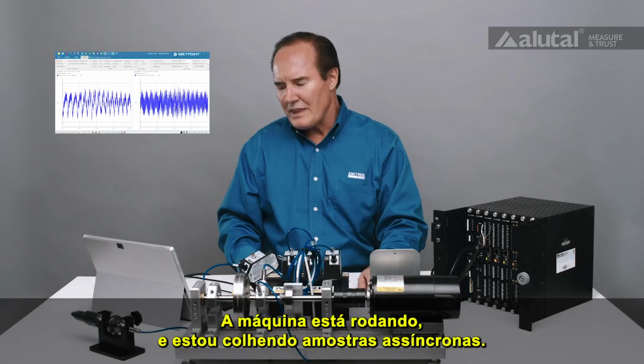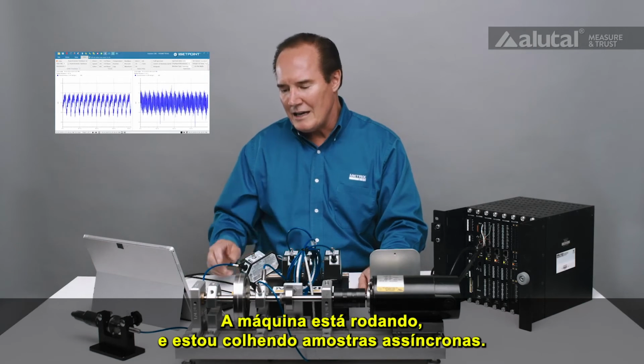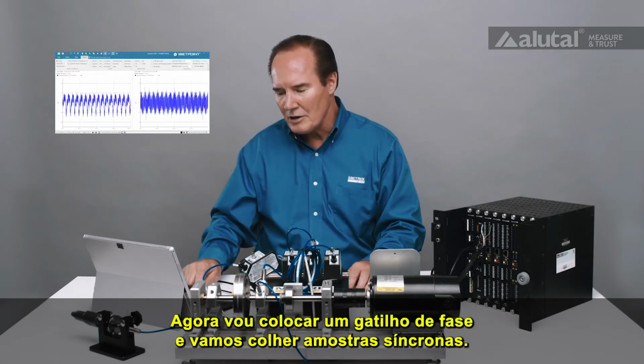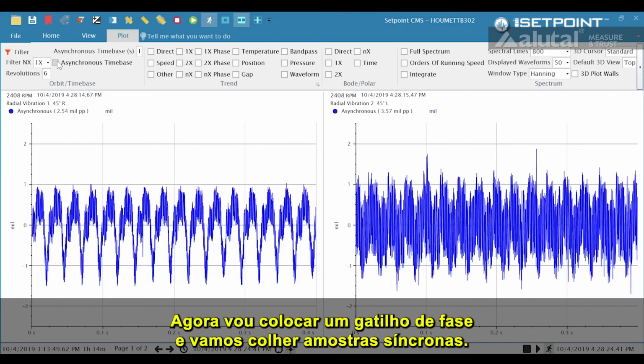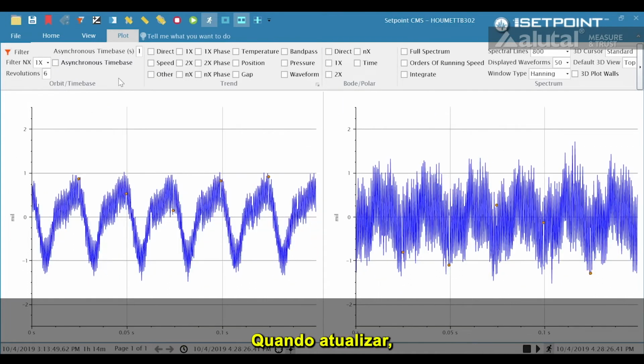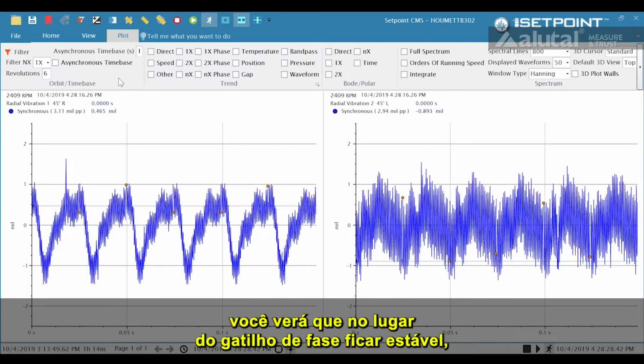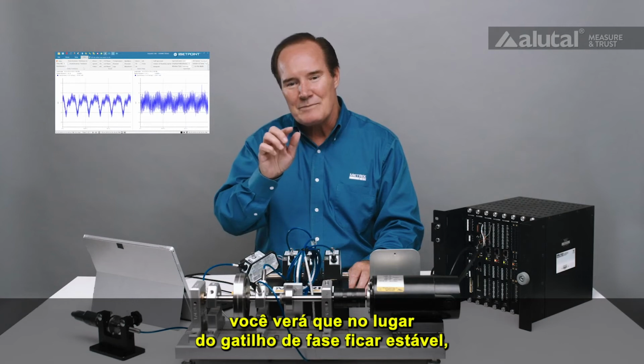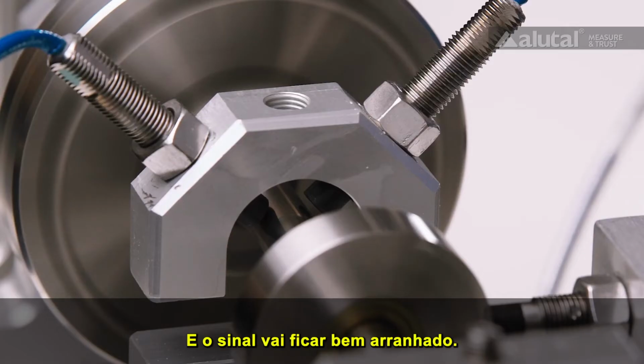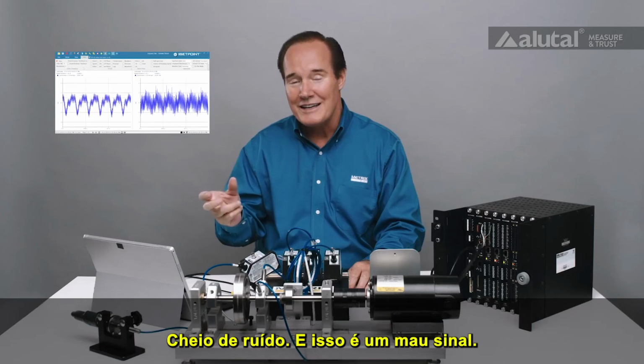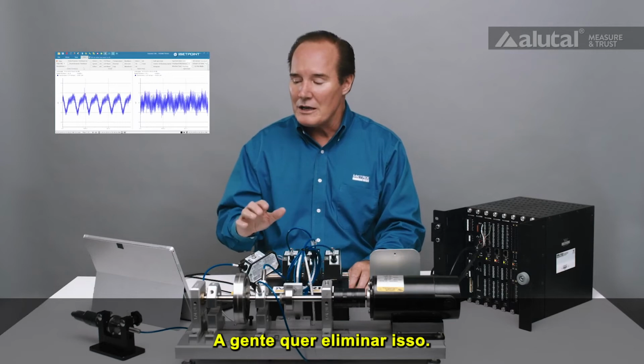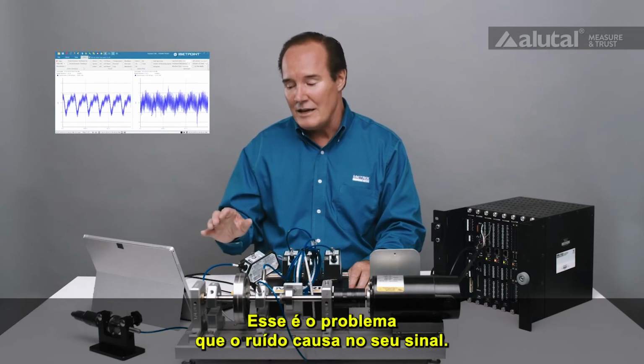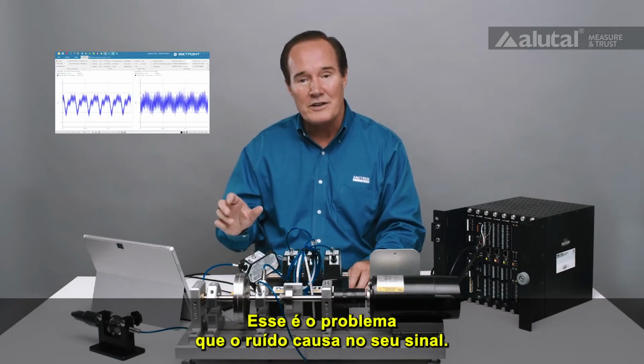All right, now this machine, you can look at it, and I'm asynchronously sampling. What I'll do is put a phase trigger in there and we'll synchronously sample. When that updates, what you'll see is that instead of the phase trigger being stable, it will be moving. And the signal itself looks very scratchy. It looks like there's a lot of noise on it, and that's all bad. We want to get rid of that. And so this is the problem that noise causes in your signal.